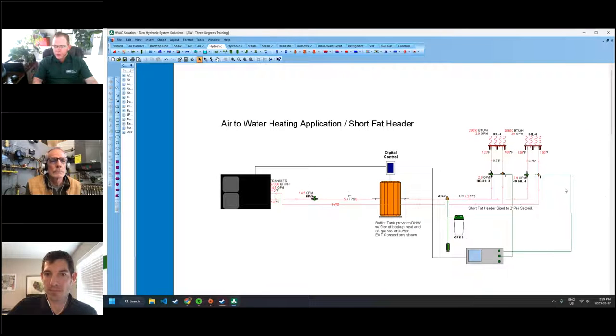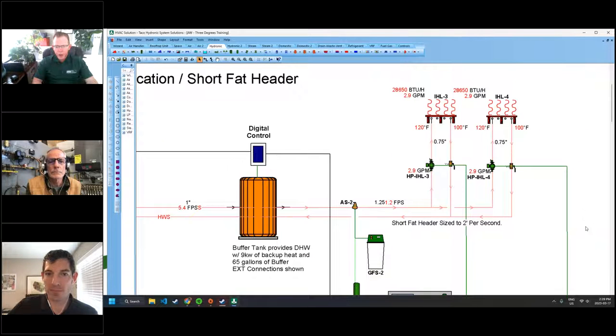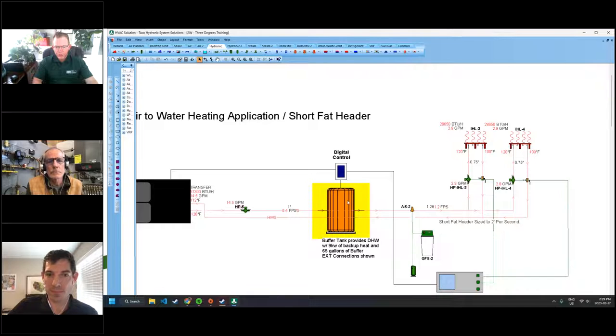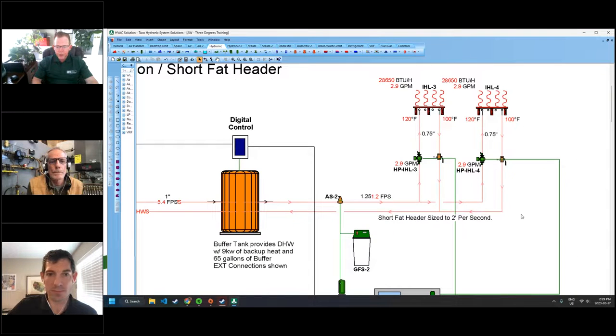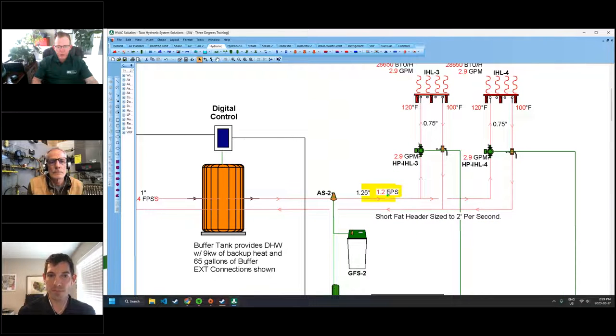So on the secondary side, one of the things I want Bob to touch on here is some of the common things. We have a buffer tank, and again, it's that Argosys buffer tank where I've got supply and return. And on the secondary side, what we've done is what's called a short fat header. And Bob, I just want you to quickly touch on that and explain for people who don't understand, because a lot of people would look at these pumps and go, wait a minute, Mike, these two pumps are going to fight each other. Can you just explain why that's not going to happen in this scenario?